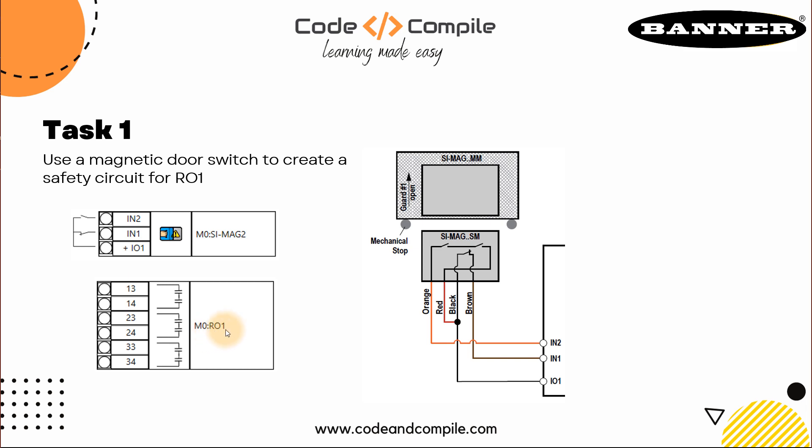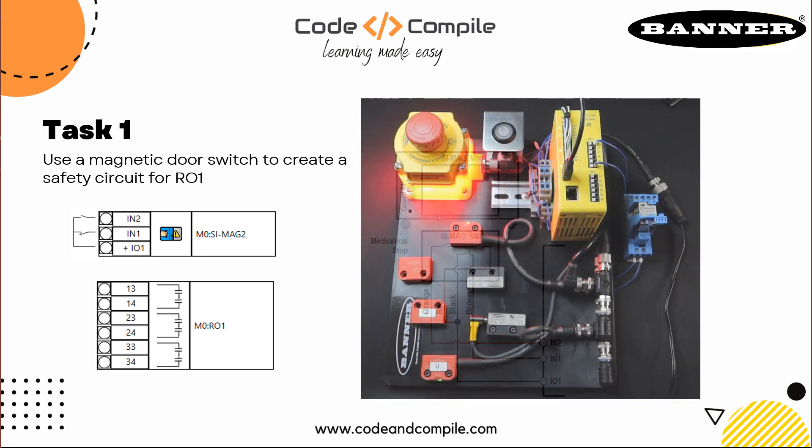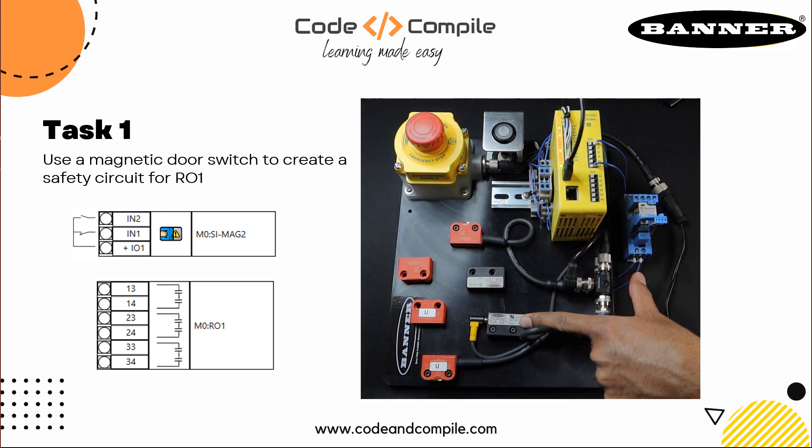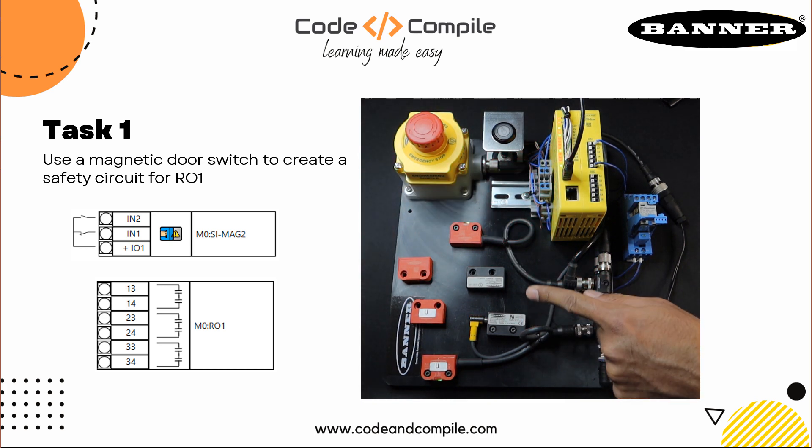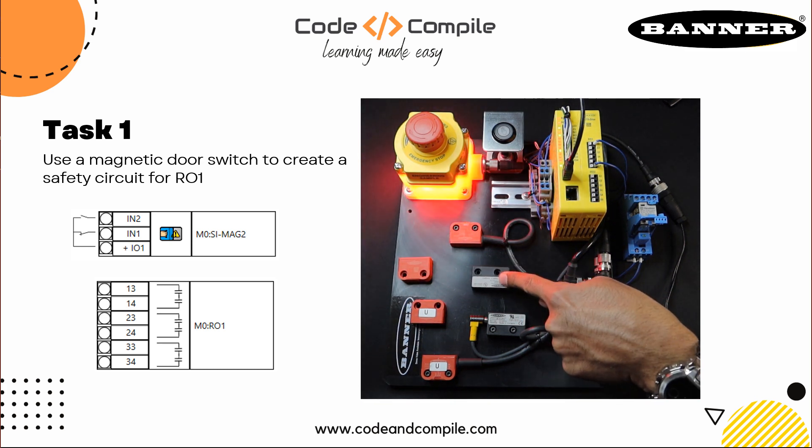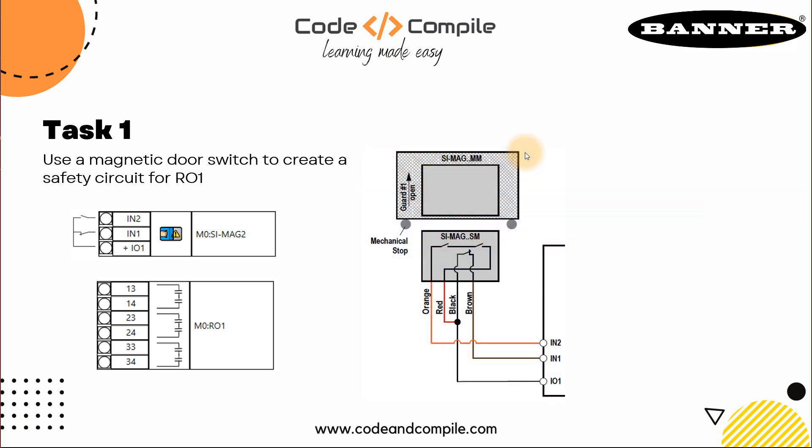This is your first relay output. And if you want to see the wiring of the sensor, it is connected to IN1 and IN2. And if you notice IN2, this is going inside the sensor and it is having some magnetic contact. And it's coming back with a loop and going back to IN1. So IN1 is having an NC contact and IN2 is having an NO contact of this magnetic switch. So magnetic switch has one part on the top, another part on the bottom. So here you can see that this is the part on the top. And that's the actuator. So we have to control the output RO1 using this magnetic switch.